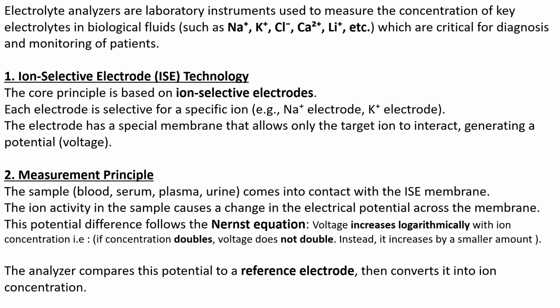The first methodology, the ISE technology. Here, the core principle is based on ion selective electrodes. Each electrode is selective for a specific ion. For example, a sodium electrode will allow only sodium ions to pass through. The electrode has a special membrane that allows only the target ion to interact or pass through, generating a potential or voltage.